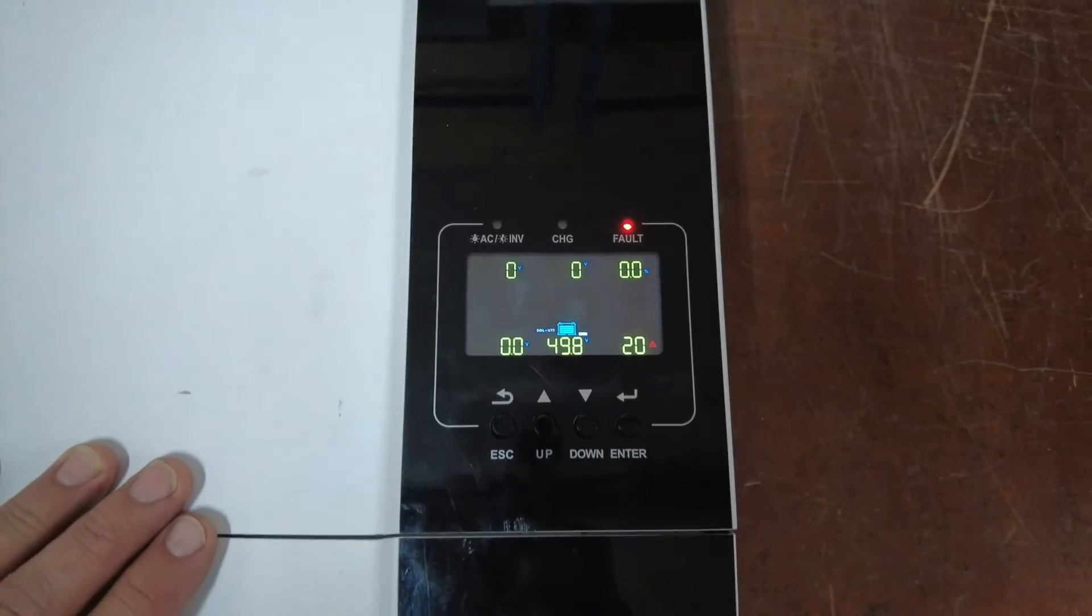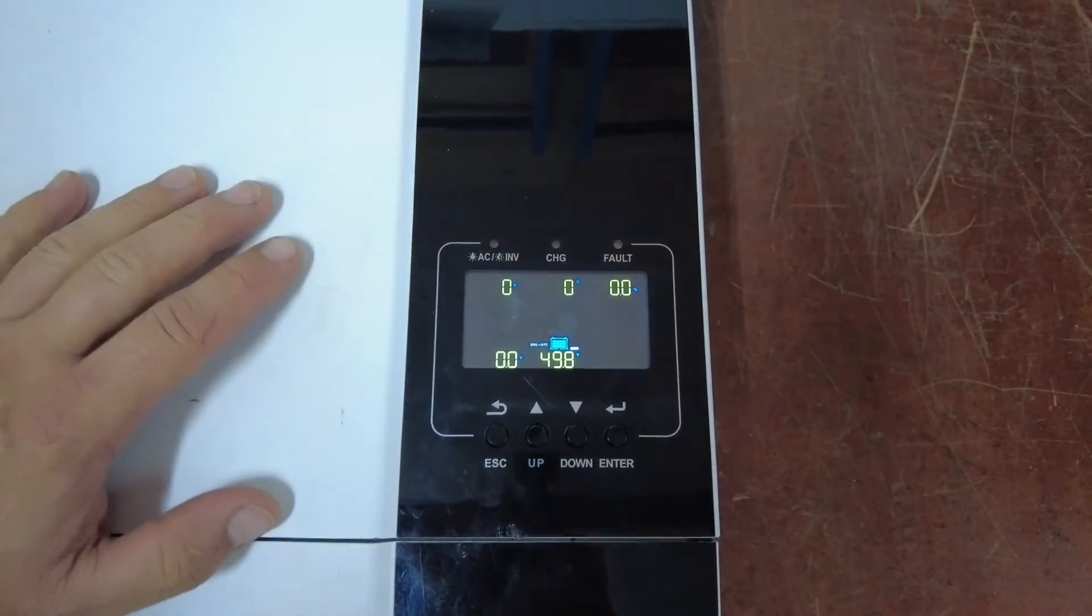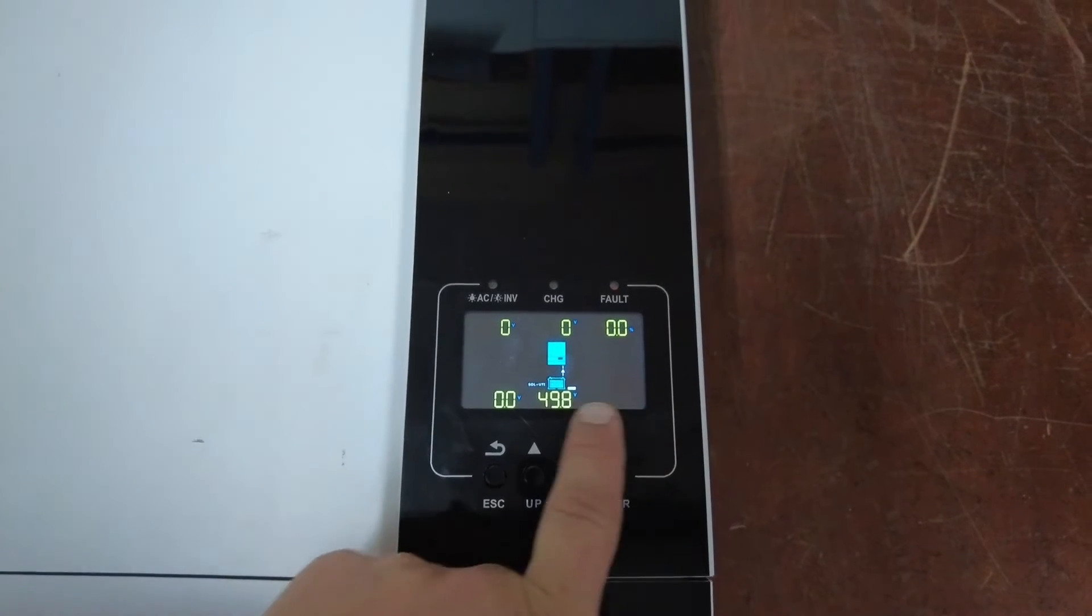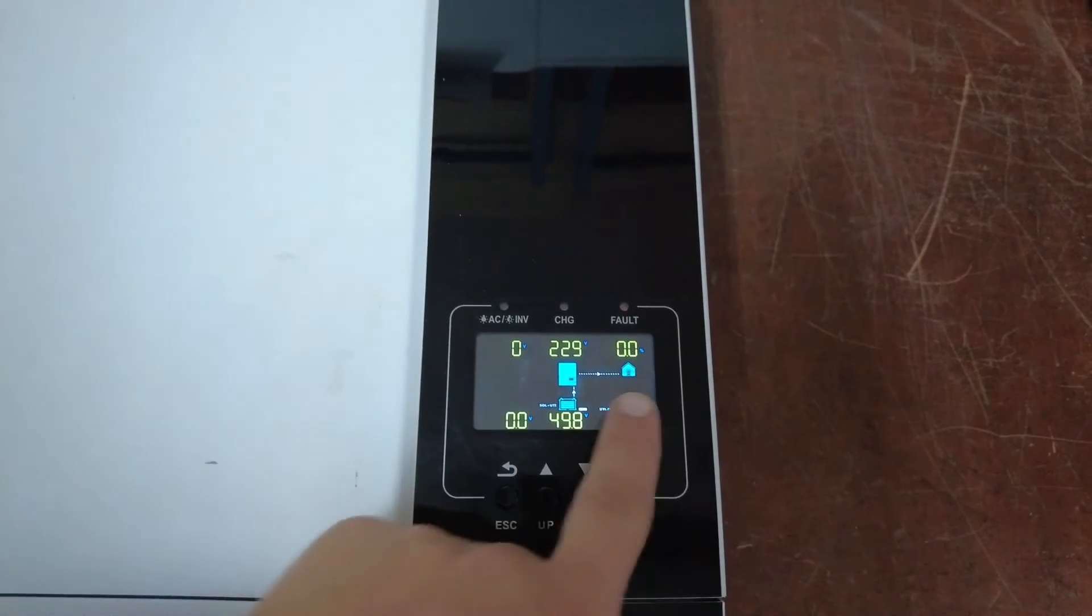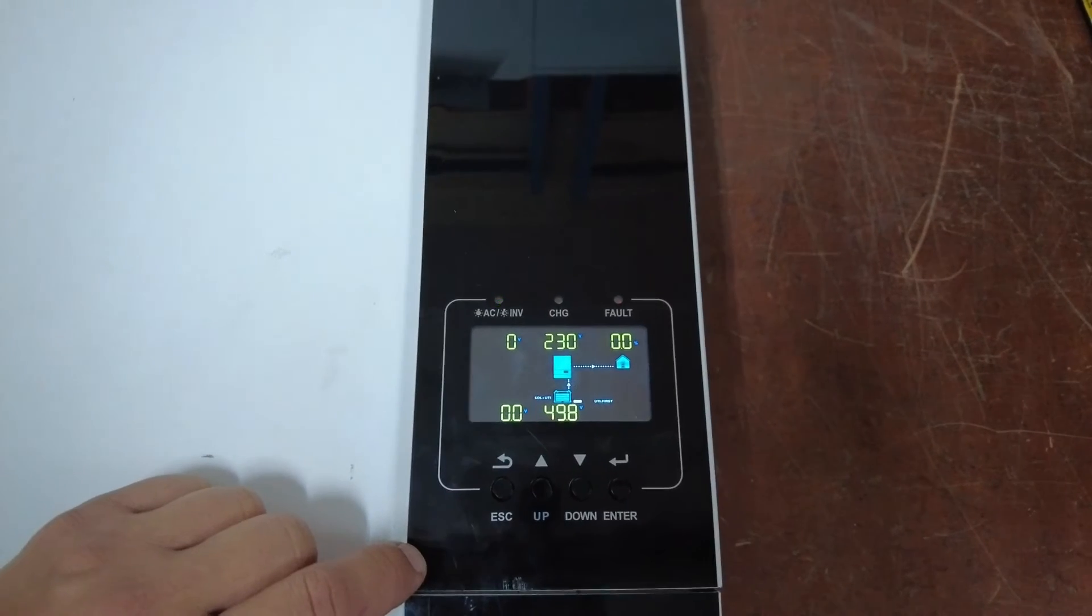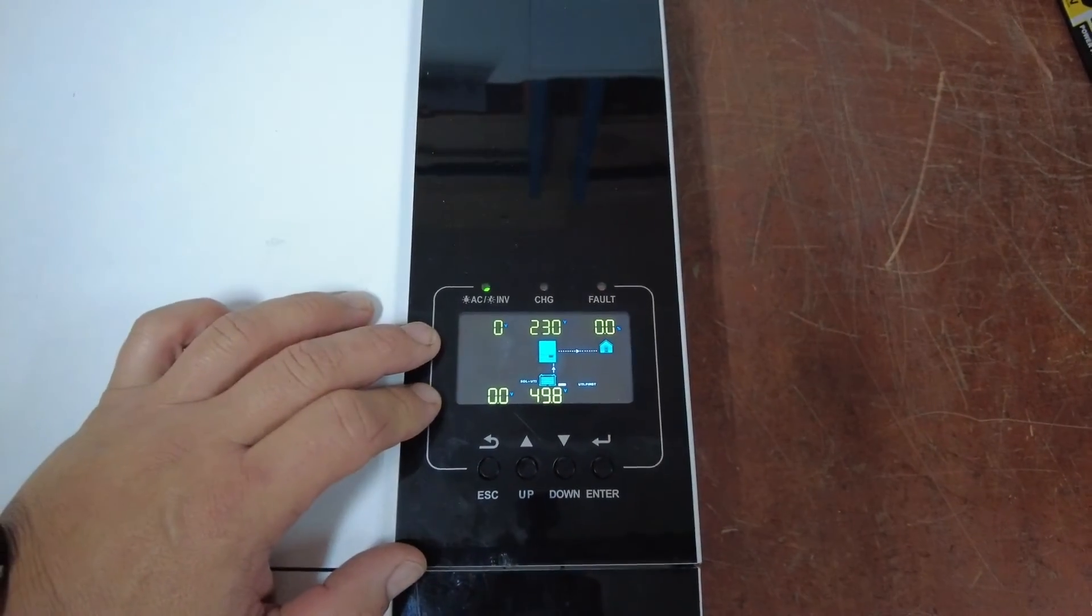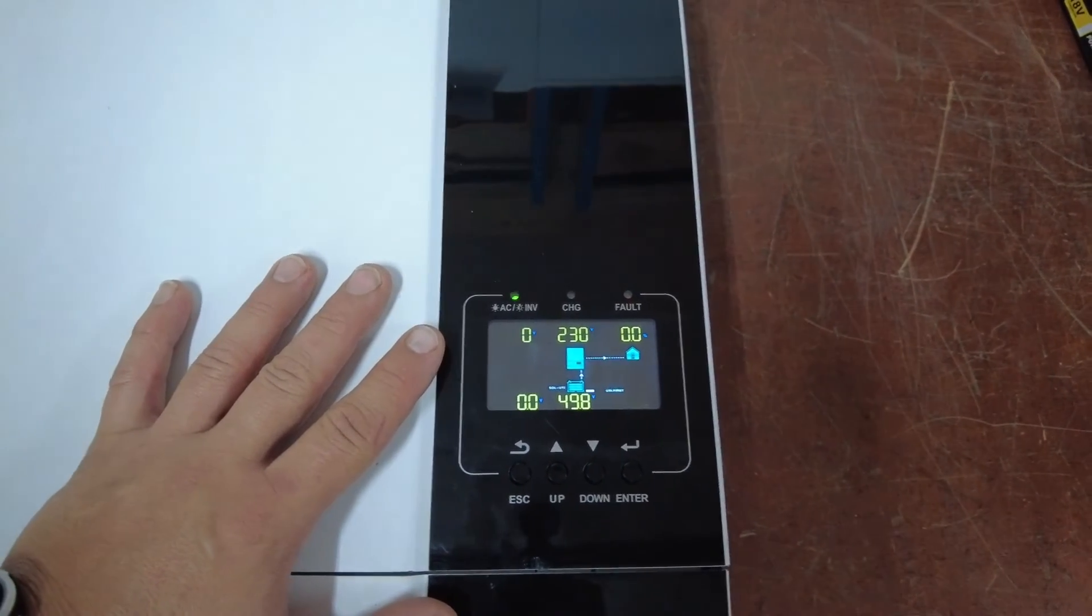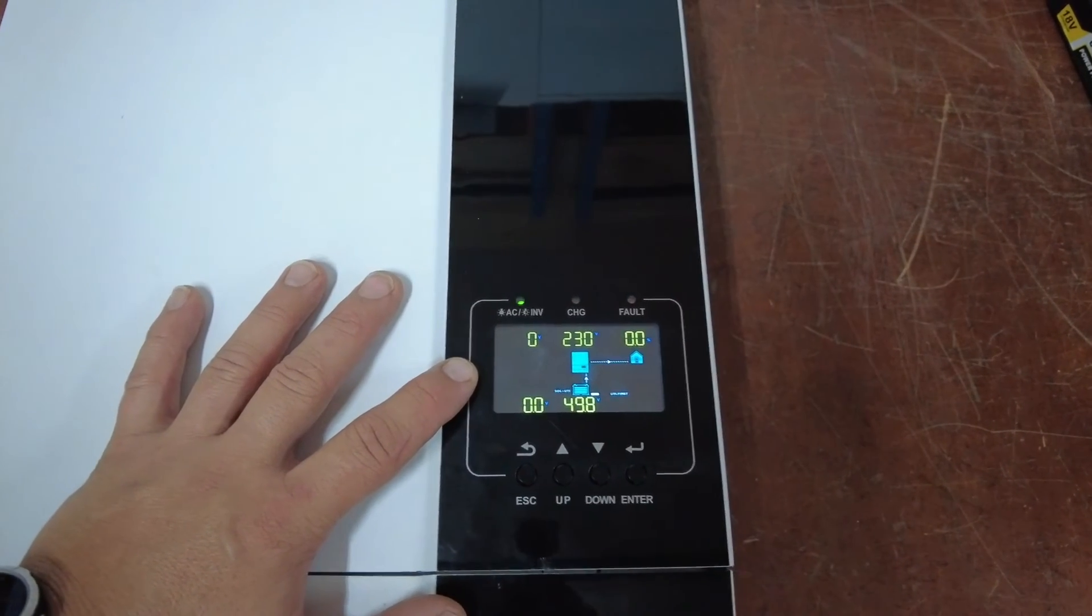Now that the cable is connected, you can see the SOC lights changed. The error has disappeared, and it's starting to communicate to push DC power through to the home. This shows the communication is successful. If the communication was not successful, as you've just seen, it will shut down and not push battery power back to the home.